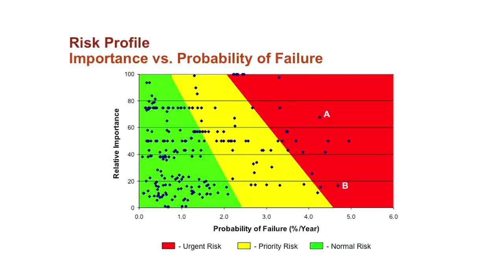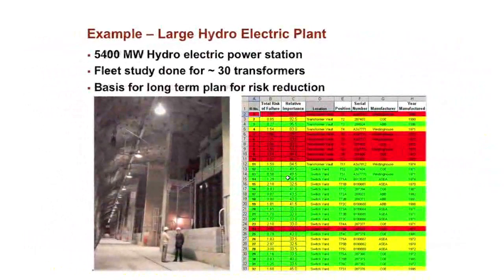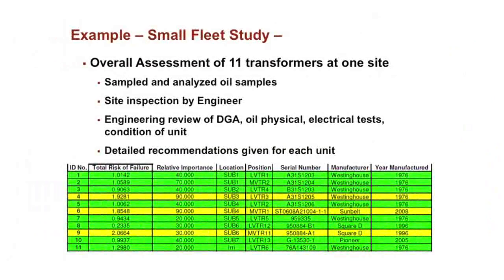Okay. So what I'm going to go through now is some different examples of risk of failure calculations. And then I'll go through what can be done to reduce or mitigate risk of failure. This is a risk of failure calculation that was done for a large hydroelectric plant. Actually, yesterday this was presented to this customer. For this one, there were 30 transformers, and the risk of failure was calculated for all the different transformers. From this fleet study, a plan was developed to reduce the red ones, and then eventually a long-term plan to replace a lot of these assets.